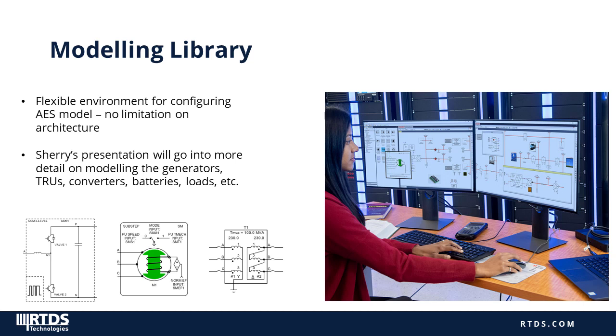Our software, RSCAD FX, is what Sherry will be demonstrating. The architecture she demos is just one example of an AES model — the software is very flexible, allowing engineers to build up their custom model reflecting whatever specifications of aircraft generation, distribution systems, and loads are required. Our library has a wealth of different models, including transformer models for representing TRUs with saturation and internal faults, models for batteries, dynamic loads, and many different machine models — synchronous, induction, and DC machines, including options for internal faults.